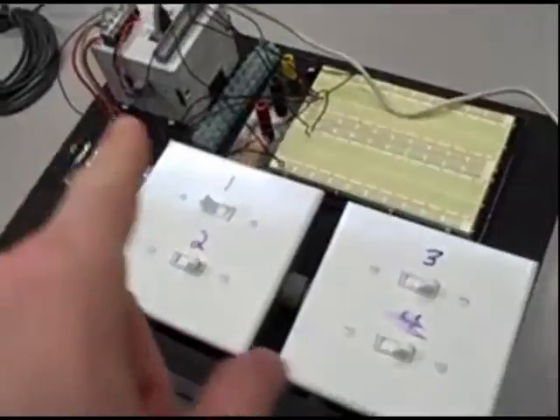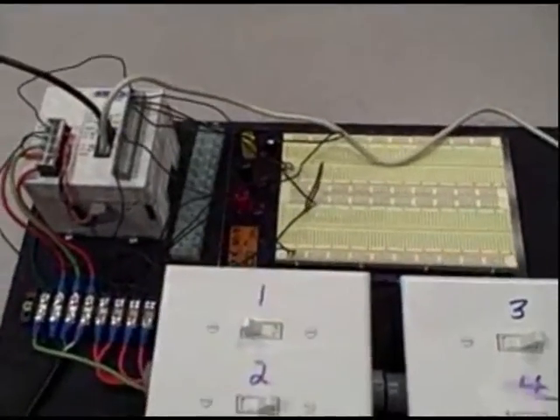Then, watch what happens when I reconnect the cable. If I go over there and reconnect, I go from a value of 37 to a value of 61, 62, 63, 64. Because, meanwhile, the master PLC never stopped timing.